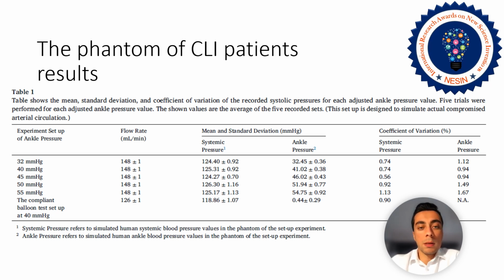Table 1 shows the mean, standard deviation, and coefficient of variation, or CV, of the recorded systolic pressures for each adjusted ankle pressure value. The shown values are the average of the 5 recorded sets. The coefficient of variation is defined as standard deviation divided by the mean, expressed as a percentage, as you may know. The CV provides a general feeling about the performance of the repeated experiment. If it is 5% or less, that generally gives us a feeling of good method performance, whereas if it is 10% or higher, it sounds bad.